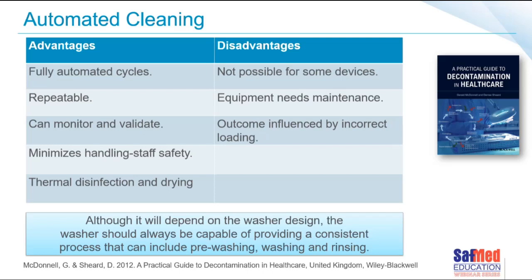We can monitor, verify and validate that the machine is working — both by looking at printouts and by using cleaning efficacy testing. Automated cleaning minimises the number of times staff need to handle contaminated instruments, which goes a long way for staff safety. There is also a thermal disinfection and drying phase. Thermal disinfection happens at a very high temperature that wouldn't be achievable in manual cleaning, and it not only protects the staff themselves but also the patients — a double-edged advantage.